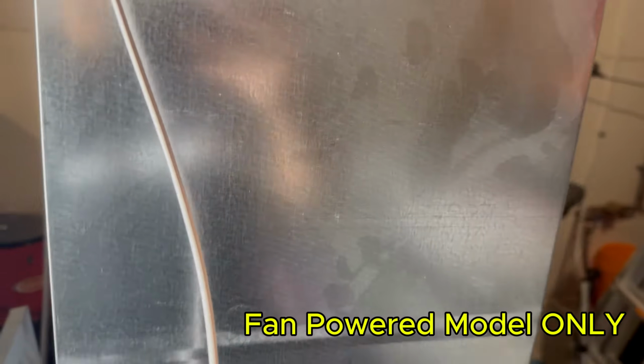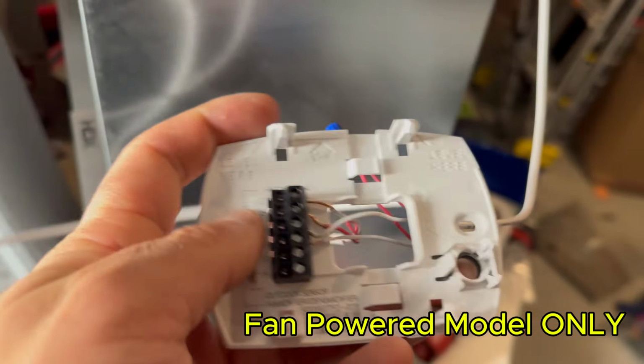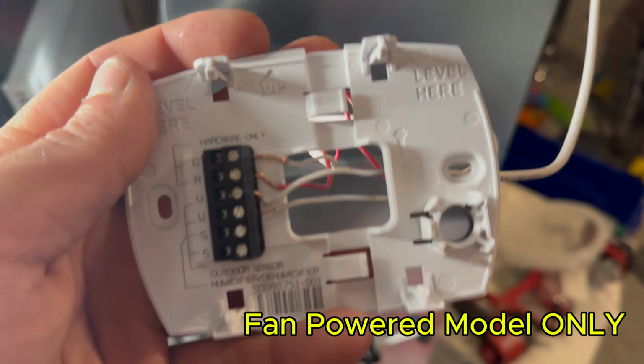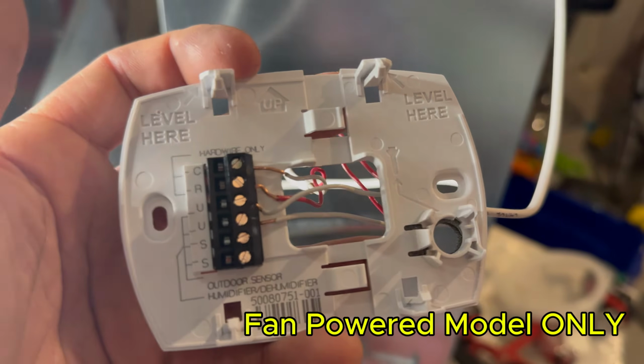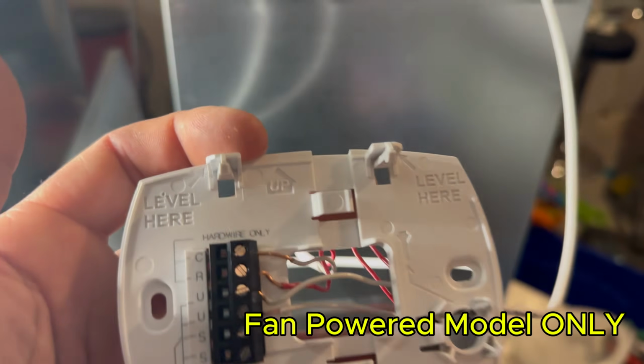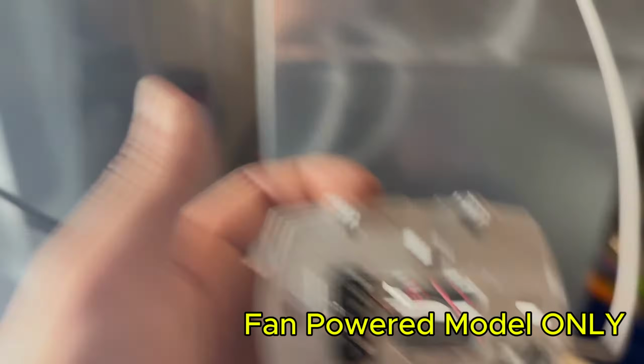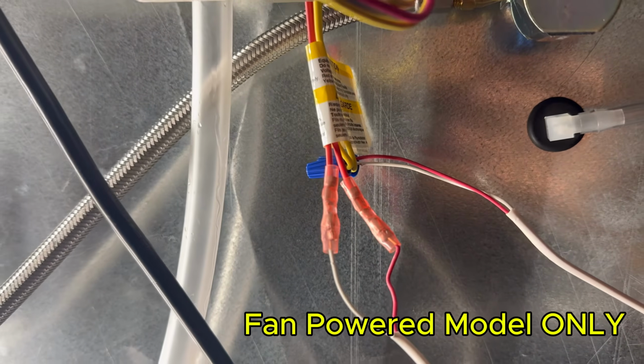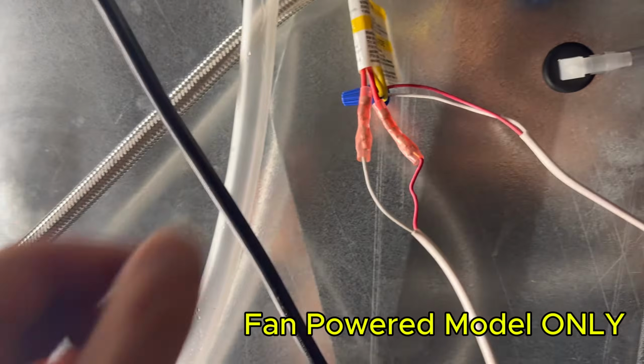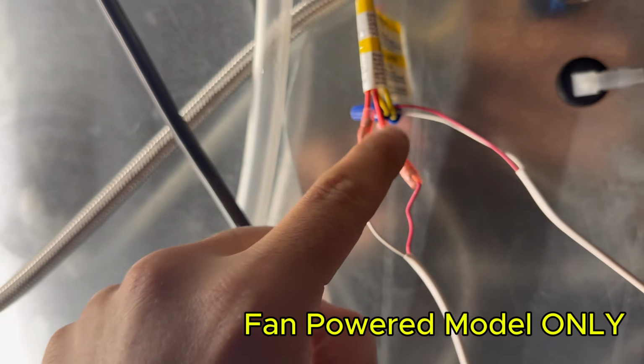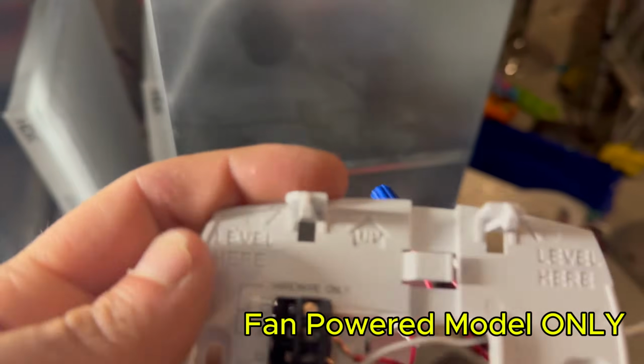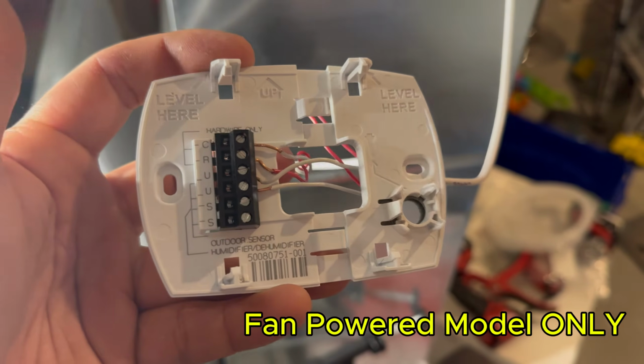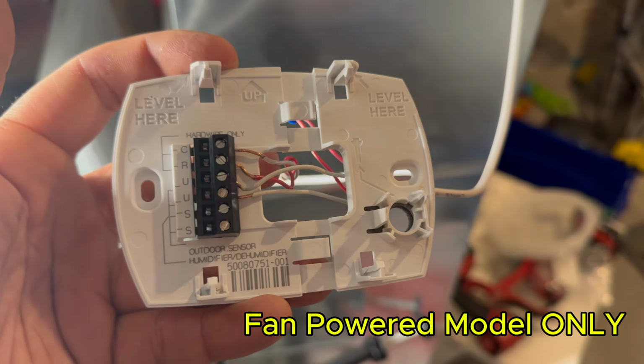But the way you're going to do this is crack open the back side of that humidistat. And what you're going to do is connect the 2 wires, both the white and the red, coming from the 2 red strands on the humidifier. So these ones here, these 2 are going to connect on the back side of your humidistat to the top, C and R.